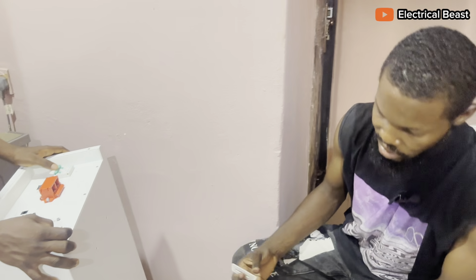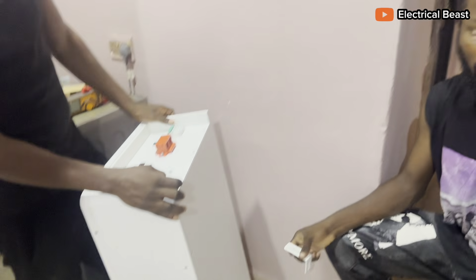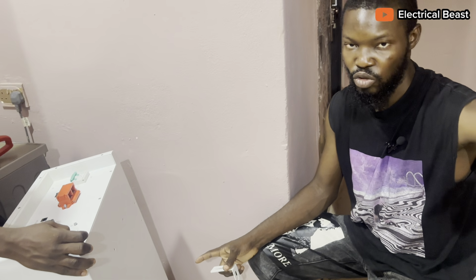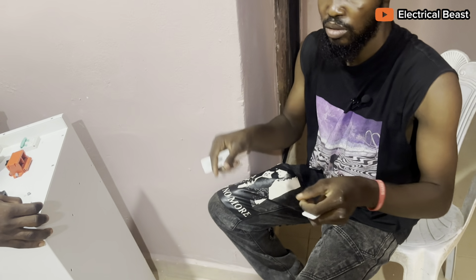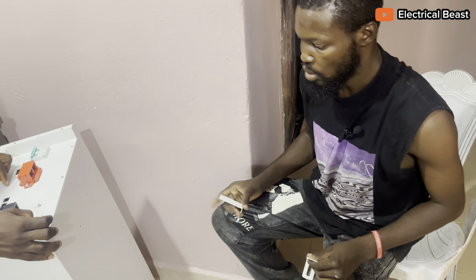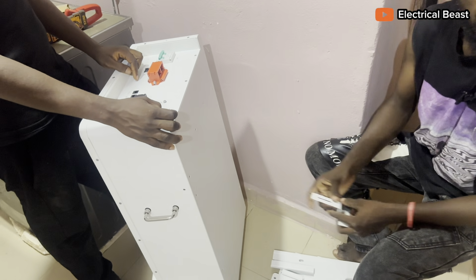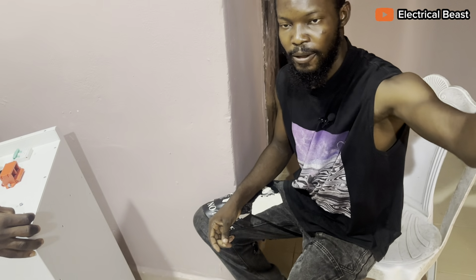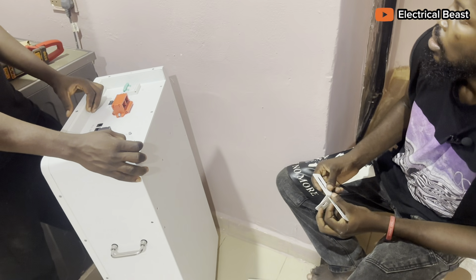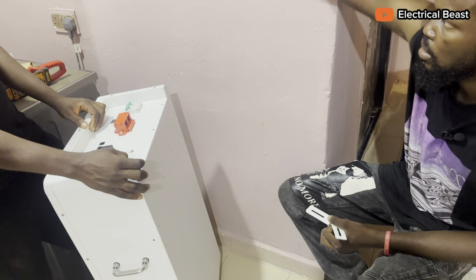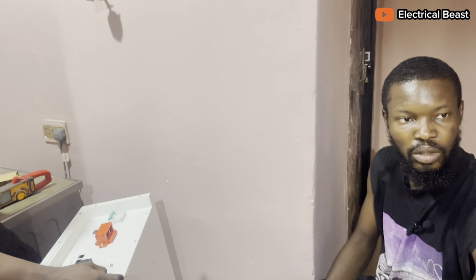I'll just fix this on the battery first. Normally we're going to mount the battery first, then start mounting the inverter on top, because the sound from the drilling could affect the batteries. So I'll fix these on the batteries and try to mount the inverter, then start the connections. We're not going to use this space because it's already compacted, so I'm going to make use of that space over there. We'll see when time comes.